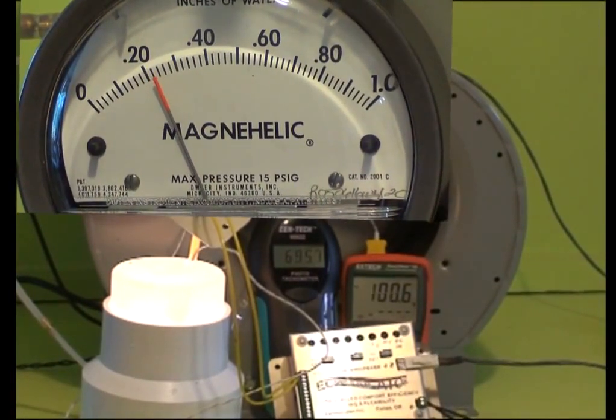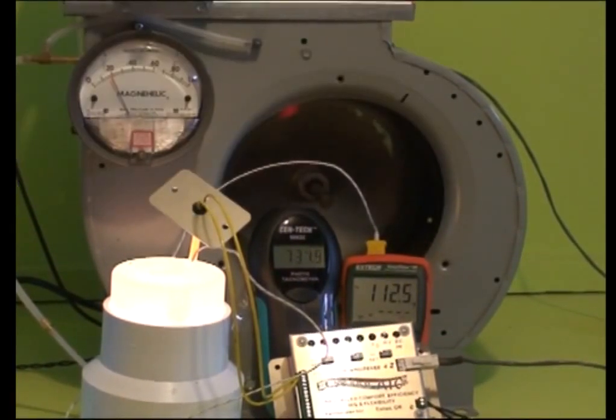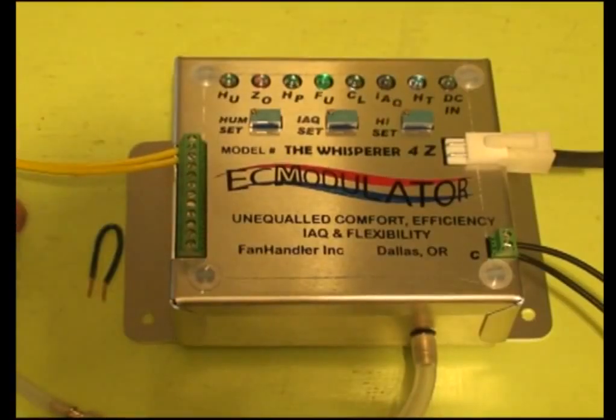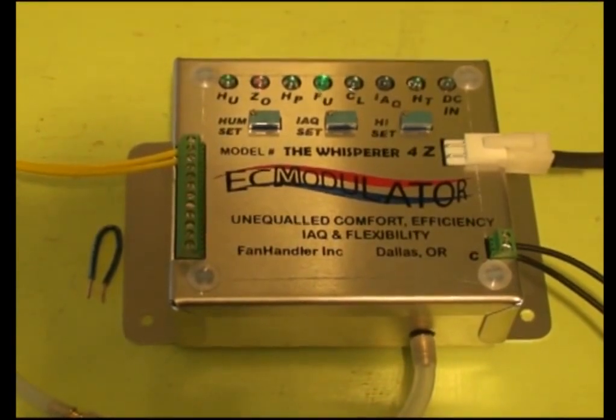The ECM modulator controls pressure by actually measuring pressure. Man, that's new. No dip switch guesswork, no flopping dampers, no noisy registers. You just saw real cruise control for zone systems. Once the pressure is set where you want it, just remove the jumper. The ECM modulator will remember your last setting.